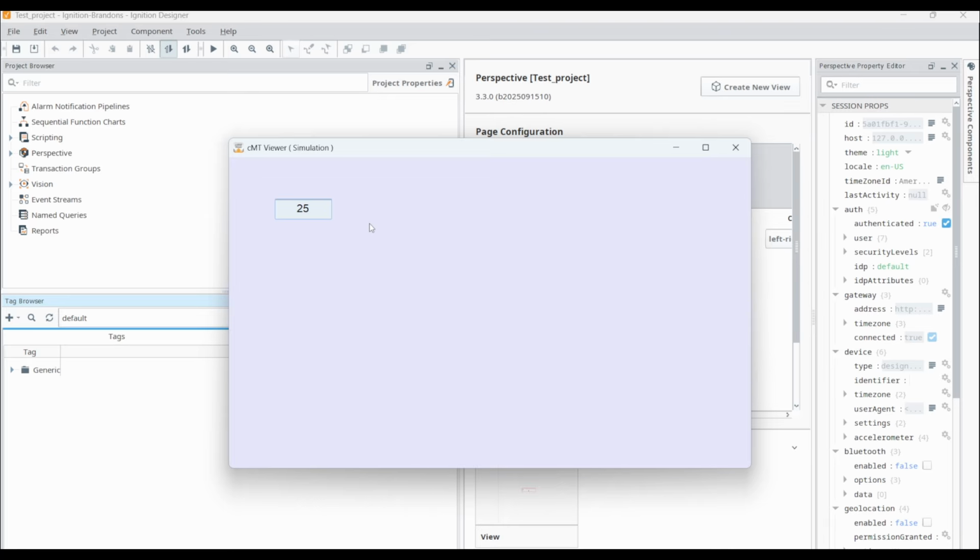And that's really all there is to it, and that's how you connect an HMI, or in this case, EB Pro's online simulation tool with the OPC UA client to an OPC UA server. So all that's left is to actually download the project to your HMI. Just don't forget to change the IP address of the target OPC UA server within the project beforehand. As I noted here, I'm using the loopback IP. So before downloading it to my HMI, I actually have to change it to my PC's IP. Typically, though, you'll be connecting to some external device, so this might not be applicable to everyone.